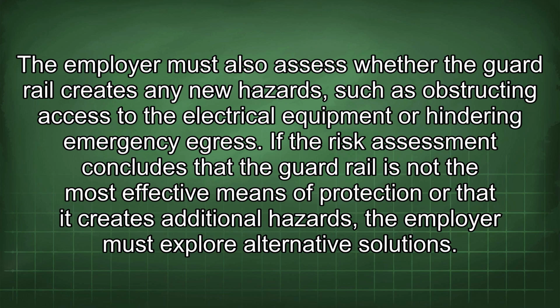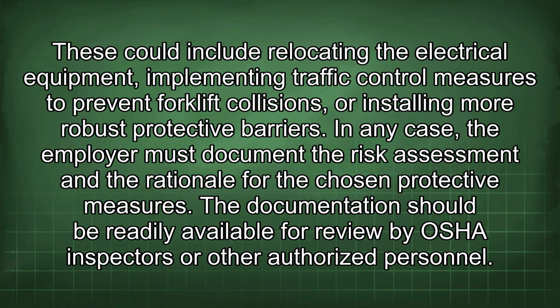If the risk assessment concludes that the guardrail is not the most effective means of protection or that it creates additional hazards, the employer must explore alternative solutions. These could include relocating the electrical equipment, implementing traffic control measures to prevent forklift collisions, or installing more robust protective barriers. In any case, the employer must document the risk assessment and the rationale for the chosen protective measures. The documentation should be readily available for review by OSHA inspectors or other authorized personnel.